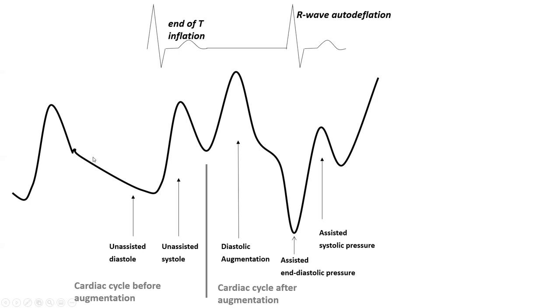Then the balloon pump console triggers based on the EKG, then it adjusts the timings based on the morphology of that waveform. And this is what should happen. Get the augmented pressure, then the pressure that follows it, which is the assisted end diastolic pressure, should actually be lower than the diastolic pressure that precedes augmentation. Furthermore, the assisted systolic pressure should be lower than the systolic pressure that precedes augmentation.